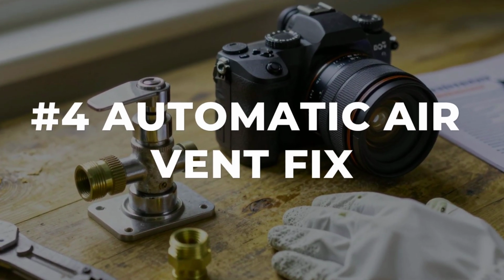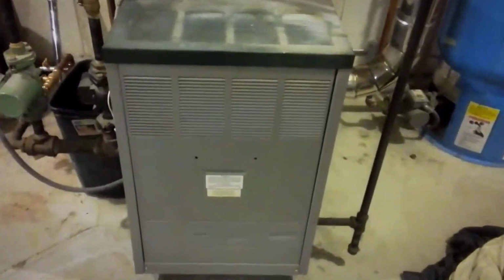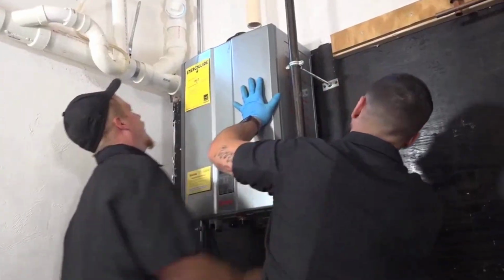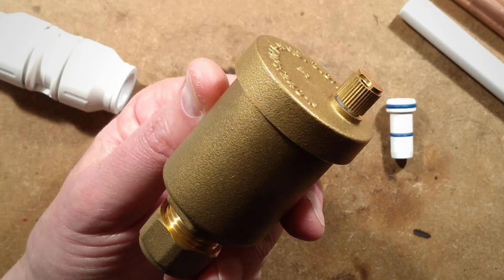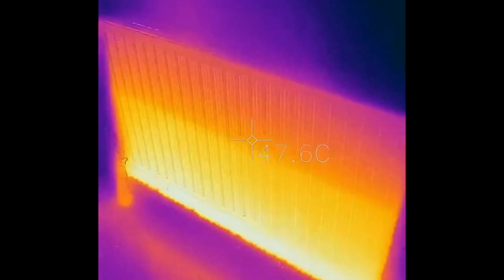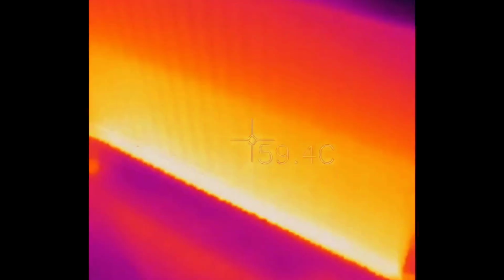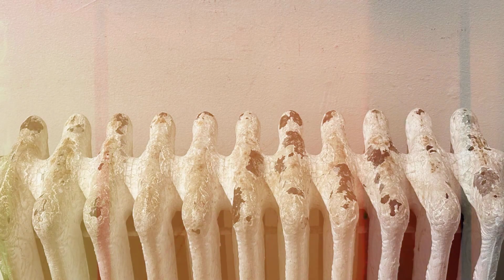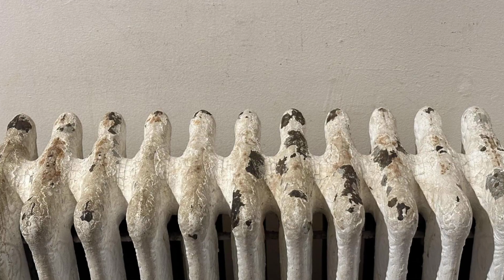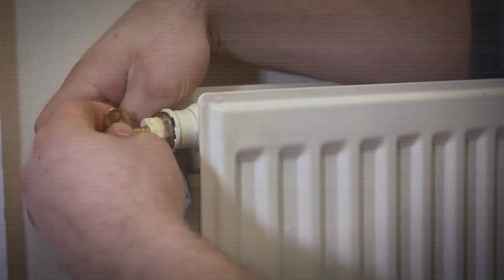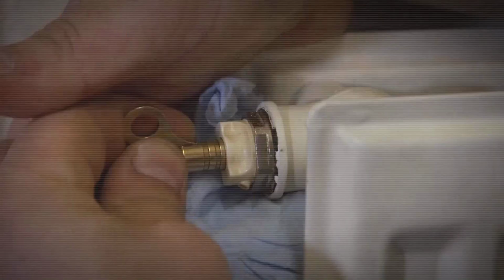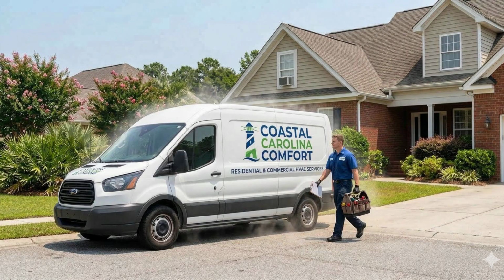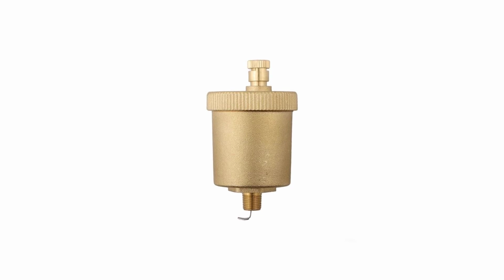Number 4, automatic air vent inspection and replacement exposes just how little it takes to keep a so-called dead boiler running for another decade. This part sits at the highest point in your system, smaller than your fist, costs less than a dinner out, and yet when it fails, trapped air will strangle heat across the whole house. The symptoms are right under your nose: a constant hiss from the vent, crusty mineral stains, or cold spots that refuse to budge no matter how many times you bleed the radiators. Here is the kicker. HVAC companies know a stuck vent mimics total system failure.